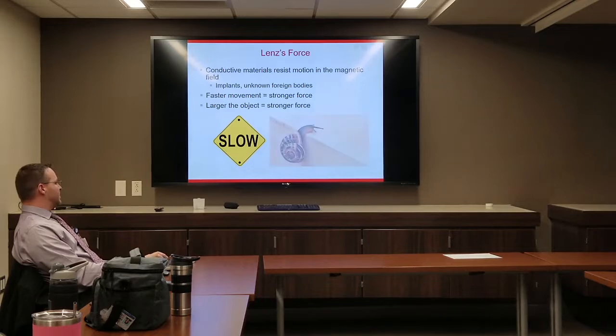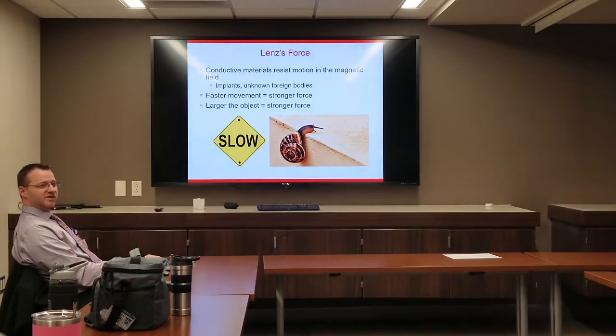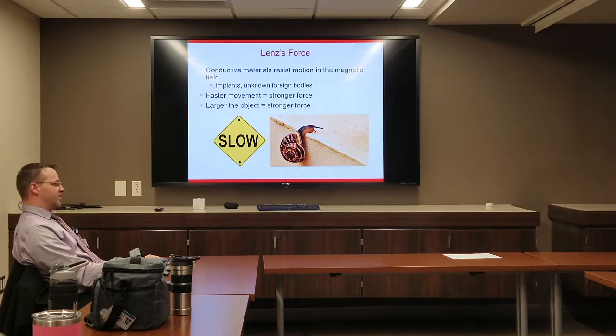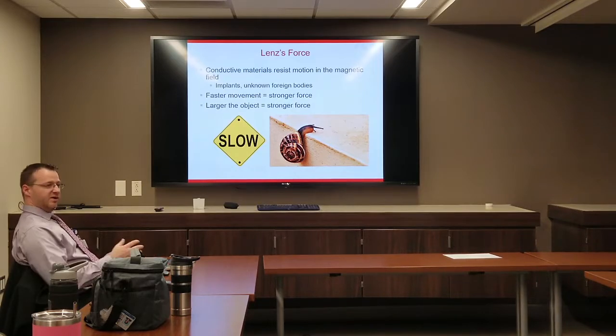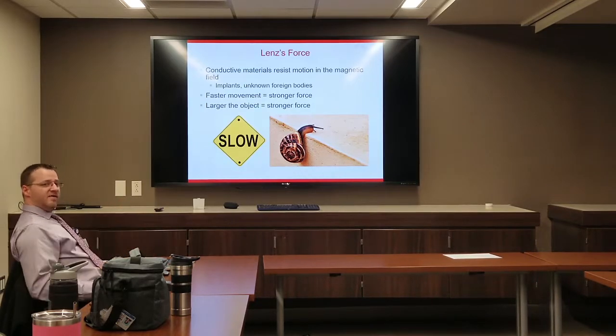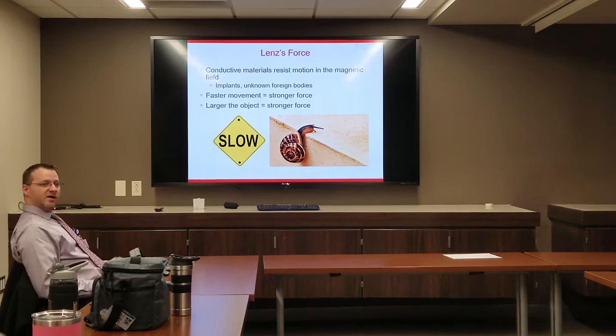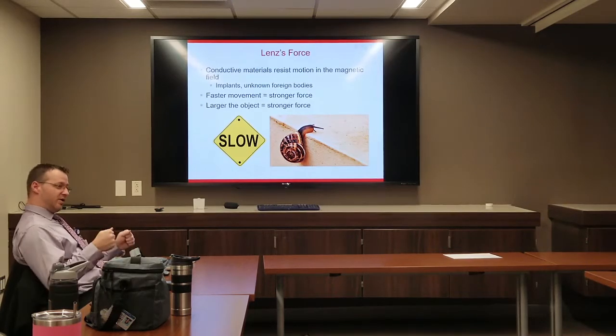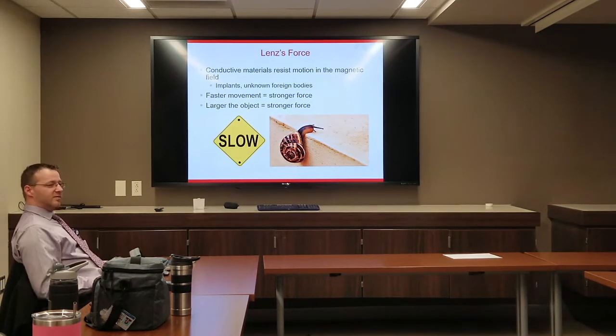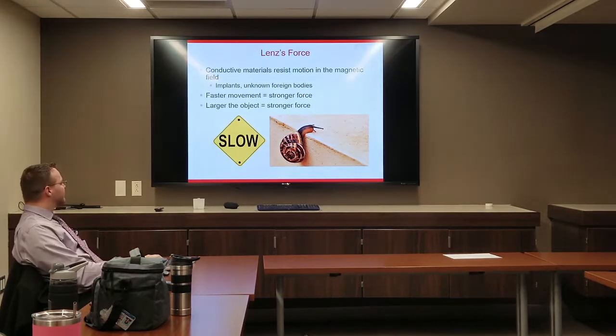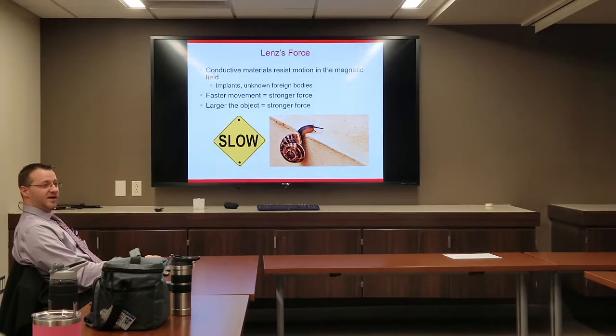Moving slowly is the safest way to go. As an example, if you hold a large aluminum pizza pan and try to move it toward the scanner quickly, it'll feel like hitting a brick wall depending on orientation. If you move it slowly, it's easier to move through. Of course, if you bring something like that in, make sure it's not ferromagnetic before you go in the room.